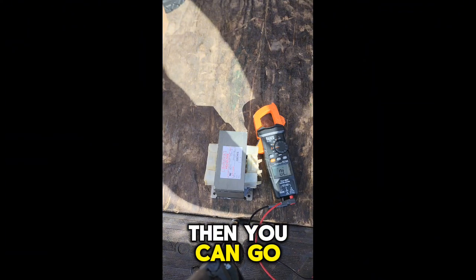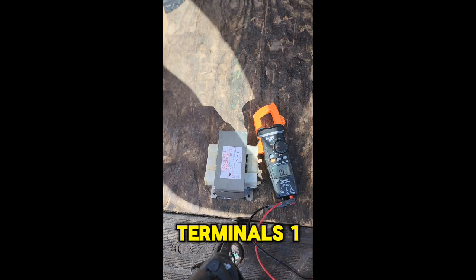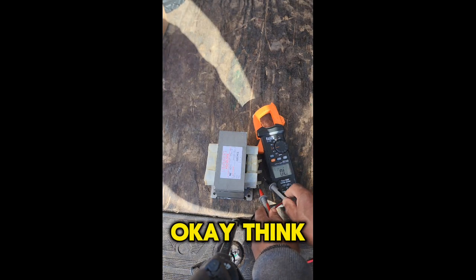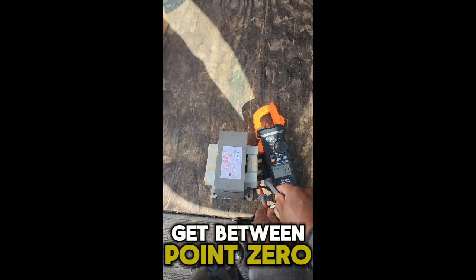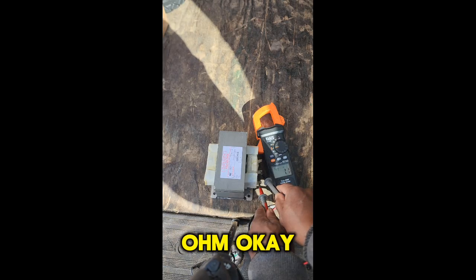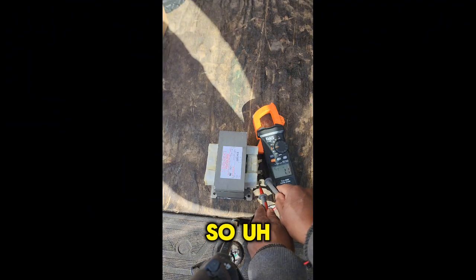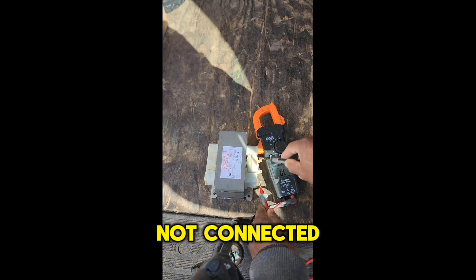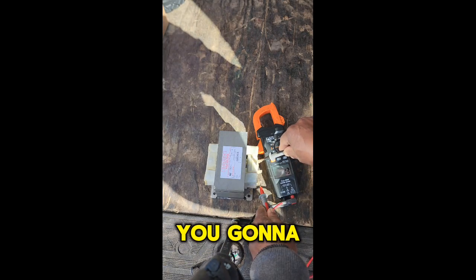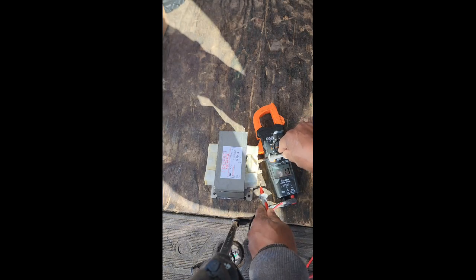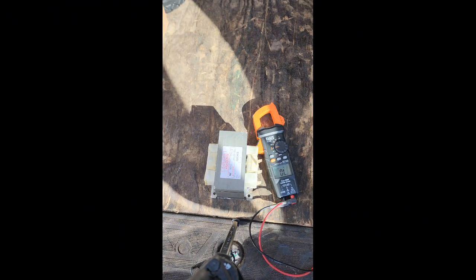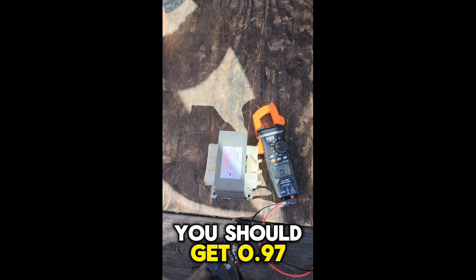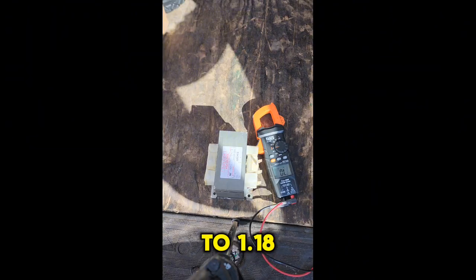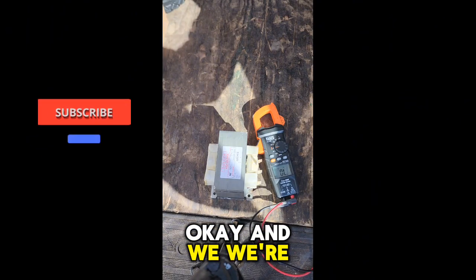And then with 208 power, you could go between terminals 1 and 2. Okay, I think you can see that. And there you should get between 0.8 to 1 ohm. I'm getting 1.1 ohm, so that's not bad, plus I'm not connected to anything. And then for 240 volt you're going to go to terminals 1 and 3, and we got 1.3. For 240 between terminals 1 and 3 you should get 0.97 to 1.18. Okay, and we're within that range.